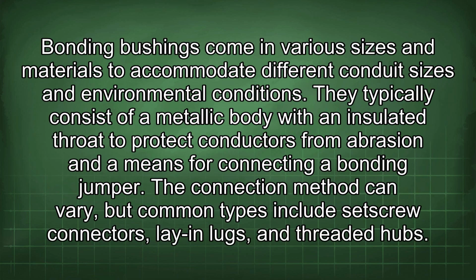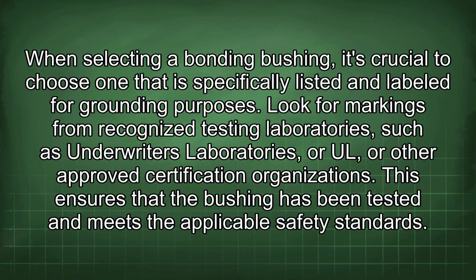Bonding bushings come in various sizes and materials to accommodate different conduit sizes and environmental conditions. They typically consist of a metallic body with an insulated throat to protect conductors from abrasion and a means for connecting a bonding jumper. The connection method can vary, but common types include set screw connectors, lay-in lugs, and threaded hubs. When selecting a bonding bushing, it's crucial to choose one that is specifically listed and labeled for grounding purposes. Look for markings from recognized testing laboratories, such as Underwriters Laboratories, or other approved certification organizations. This ensures that the bushing has been tested and meets the applicable safety standards.